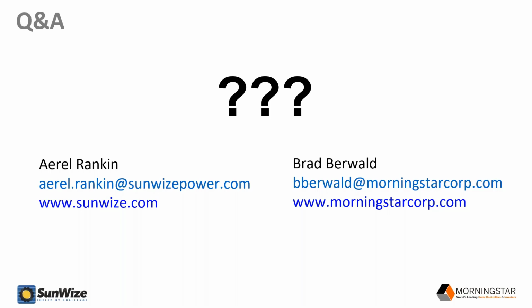Yeah, sure, this is a good, interesting question. I believe the component level certification in most cases is independent of the configuration in which it's used or the other auxiliary devices around it. Brad, does that jive with your understanding as well, in that if you put a Sunsaver that's Class 1 Division 2 in a certain location, in a certain application, there's nothing really you can do around it that would take away the Class 1 Division 2 certification rating of that Sunsaver component? Does that jive with your understanding?